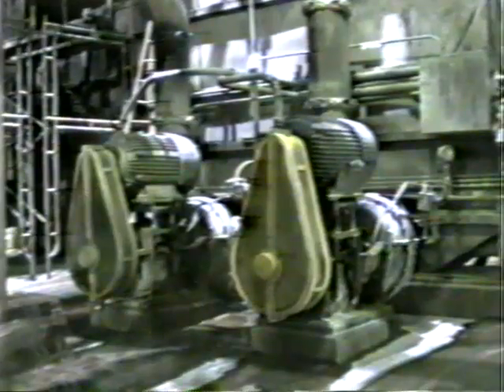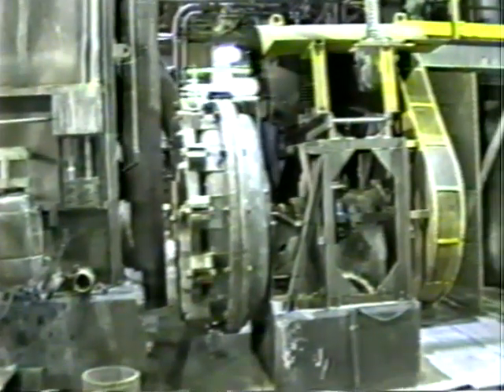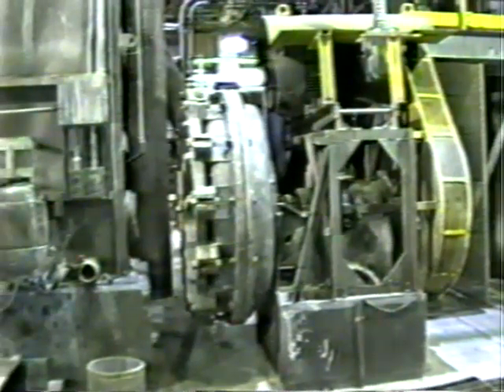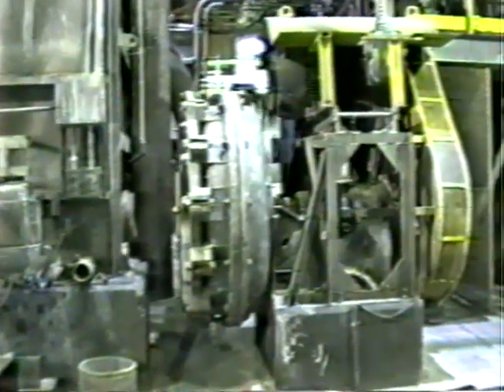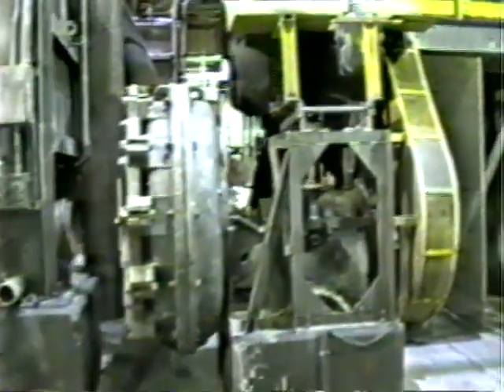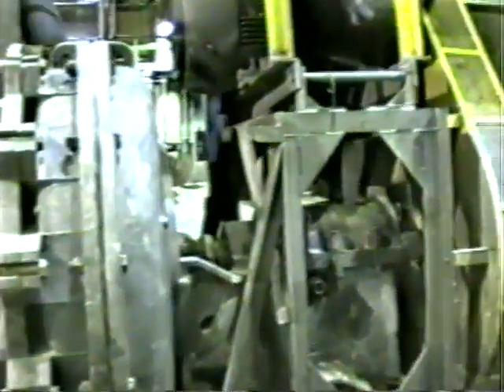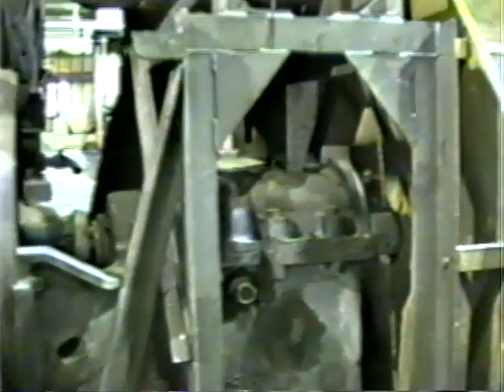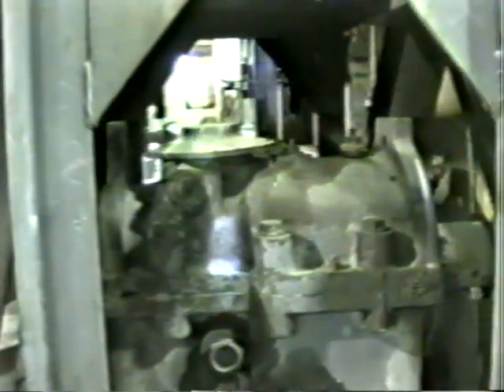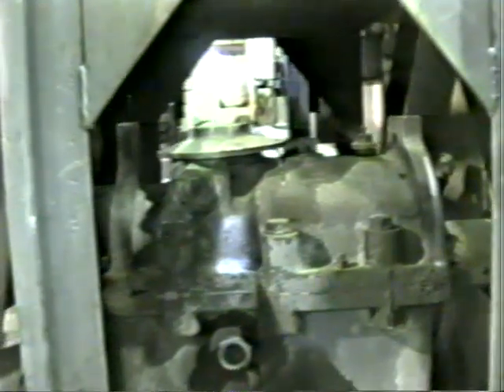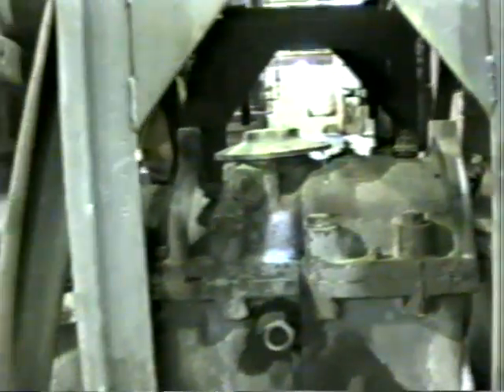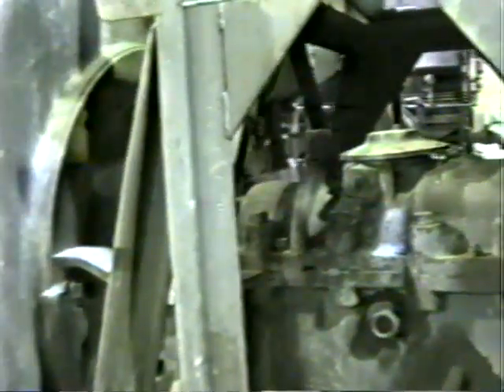each. And all the process pumps that are oil bath bearings, we added a rust inhibitor into the bearing cavities, loosened the drive belts up, split the pump cases apart, washed them all out, and reassembled the pump cases. The bearings on the pumps, which are a greased bearing system, we purged all the bearings and seal areas to seal up those bearing cavities.